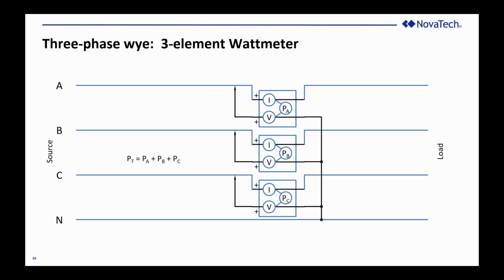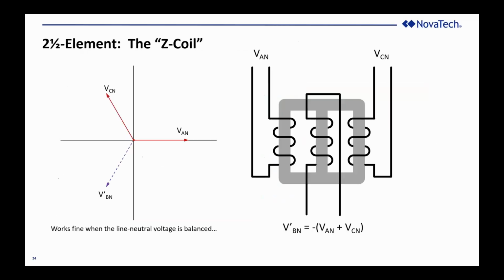So I don't think a lot of explanation needs to go into why the sum of the A phase element plus the B phase element plus the C phase element equals the total amount of power that is consumed by the load. I think we can stipulate that moving forward as intuitive. Now, I'm going to go off on a tangent here and talk about a 2.5 element meter. And I'm going to talk about a 2.5 element three-phase wattmeter using terminology that I've come to understand is not globally recognized. I've done some Google searches for the Z coil. I have to apologize. I'll tell you where I got the terminology.